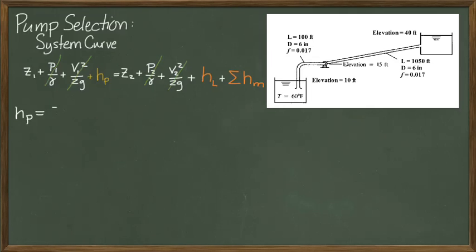So we can solve this equation for what is often referred to as the pump head by moving Z1 over to the right hand side and being left with these terms: Z2 minus Z1 plus the friction head loss plus the minor head losses.